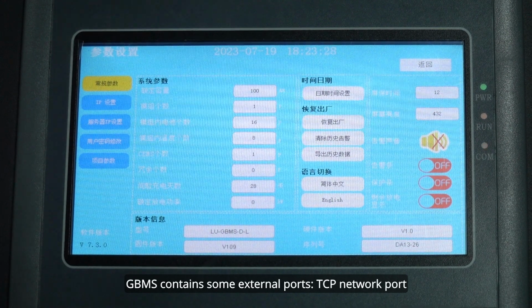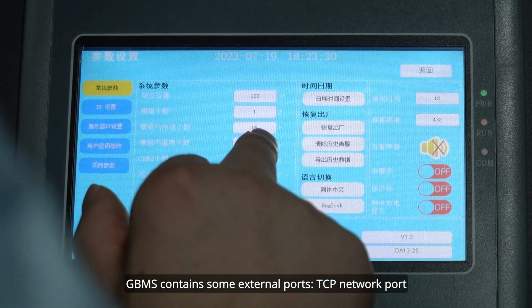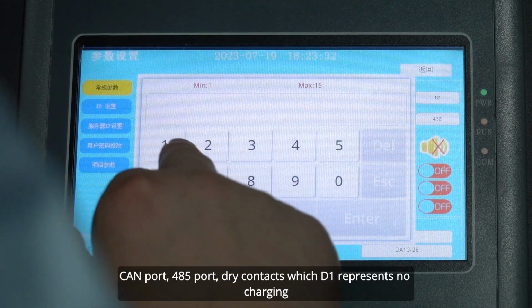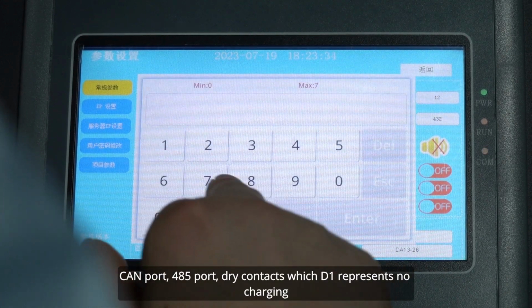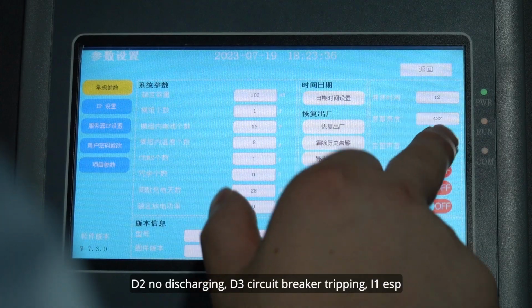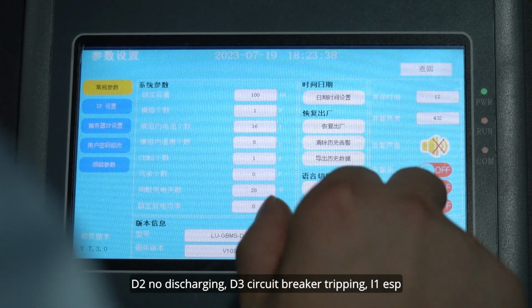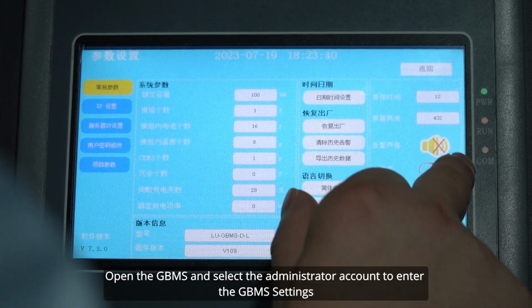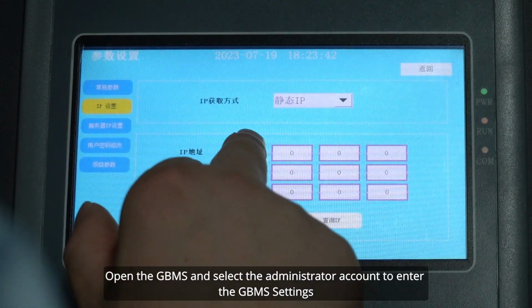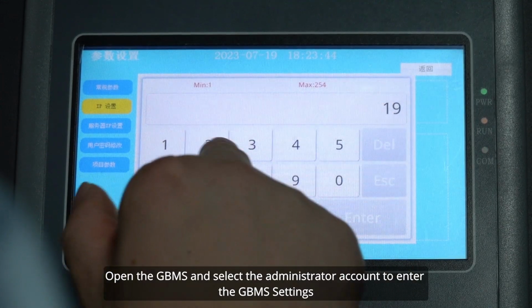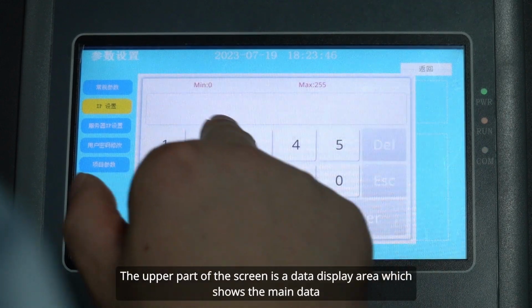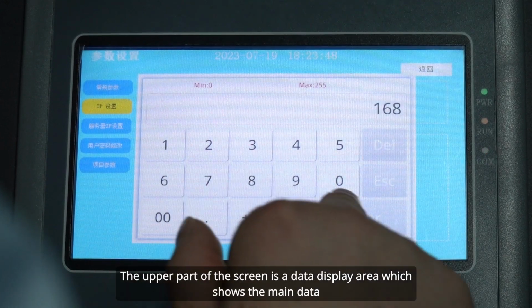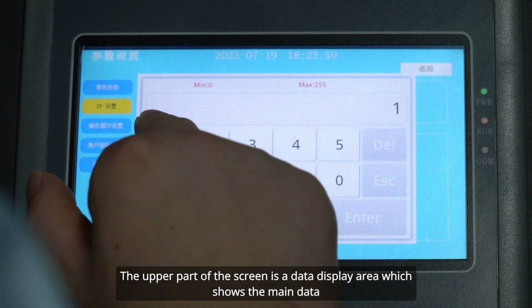GBMS contains some external ports: TCP network port, CAN port, 485 port, dry contacts which D1 represents no charging, D2 no discharging, D3 circuit breaker tripping, I1 ESP. Open the GBMS and select the administrator account to enter the GBMS settings.